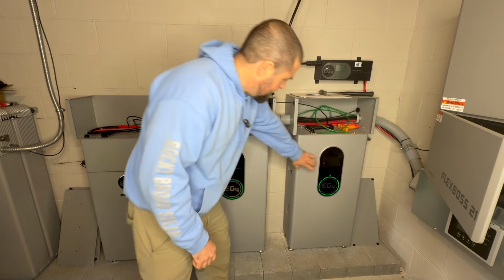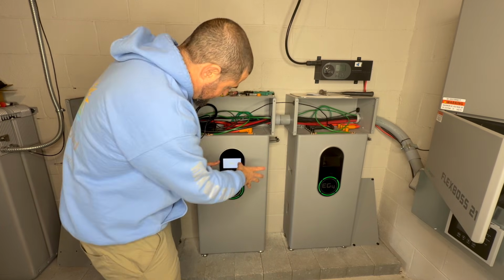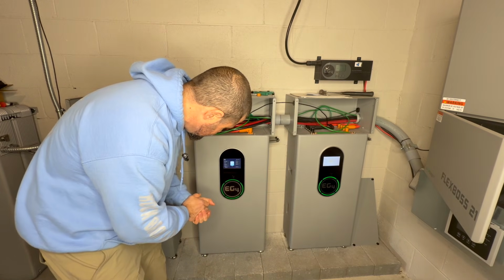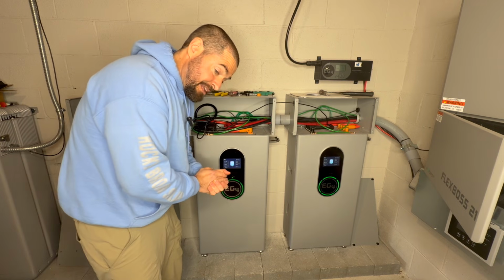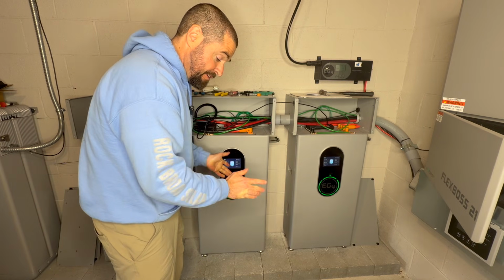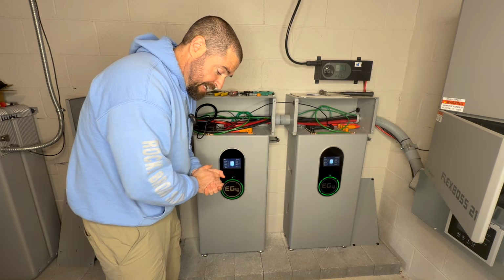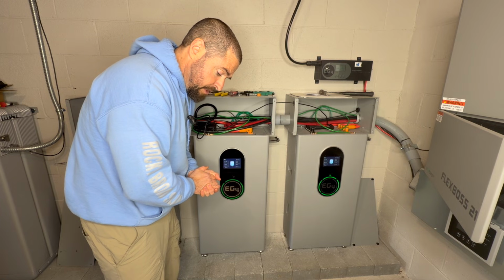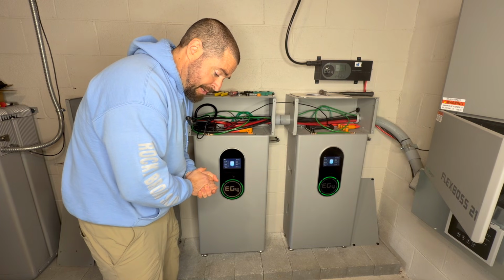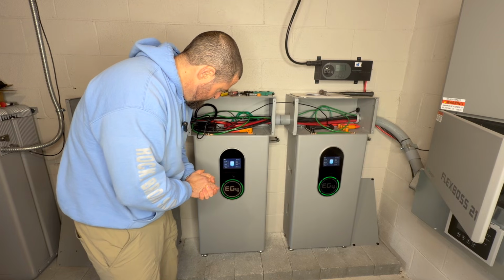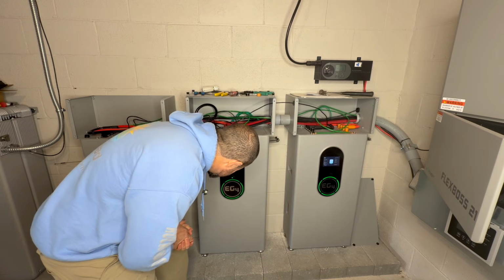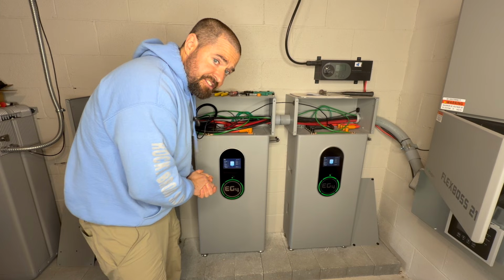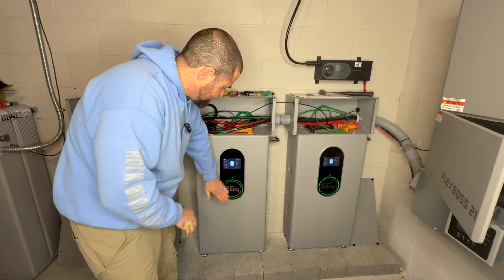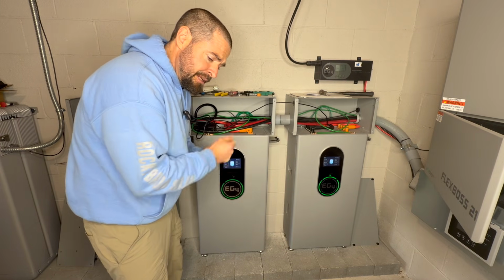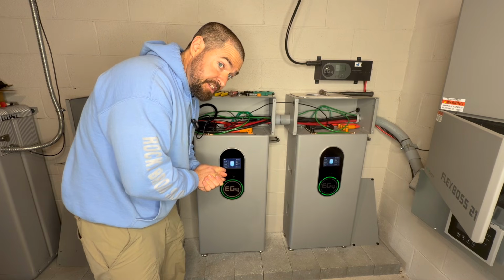So at this point, I'm just waiting for these two batteries to get up to 100% state of charge, because what they tell you in the manual is to make sure that every single battery is at the same state of charge before putting them in parallel and commissioning them. So we're sitting at 86%. I'm going to let this run until they're charged up to 100%, and then we'll go ahead and go through the commissioning process.